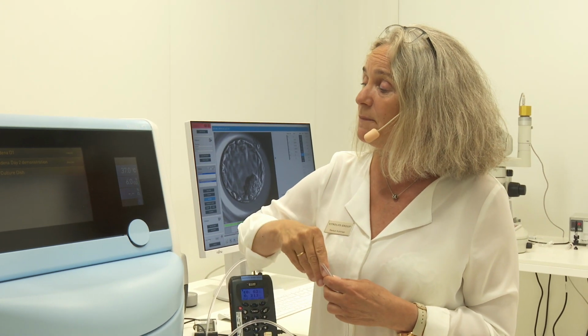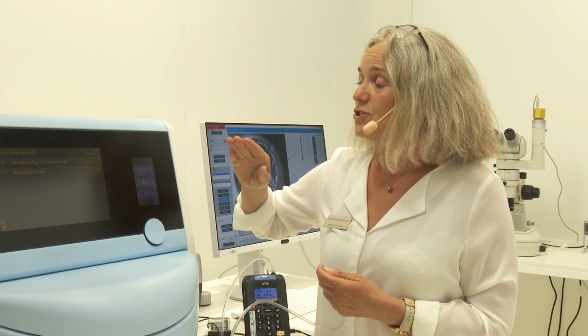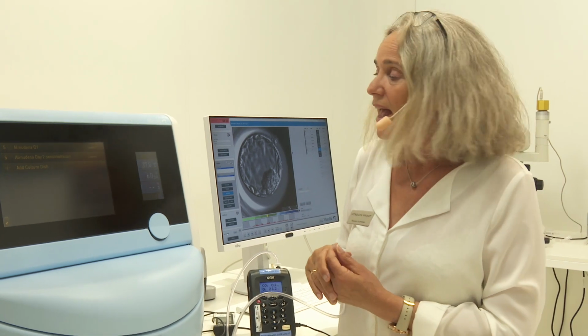For this demo system here, we have only added CO2. And you know the CO2 is how it's regulating the pH in the medium. So it should be within the right range. And the set point that you set is, of course, set according to the manufacturer of the medium. And for Vitrolife medium, it is 6.0. Being at sea level is important.